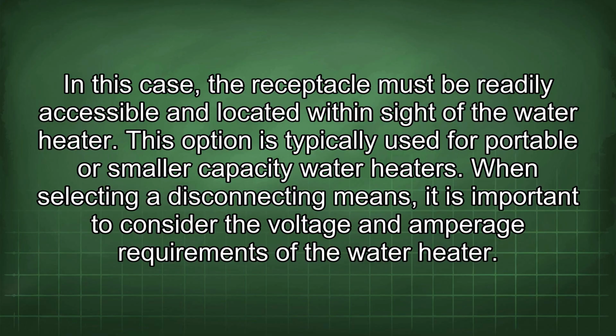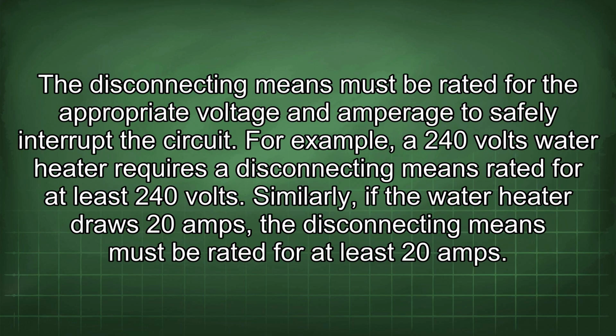When selecting a disconnecting means, it is important to consider the voltage and amperage requirements of the water heater. The disconnecting means must be rated for the appropriate voltage and amperage to safely interrupt the circuit. For example, a 240 volts water heater requires a disconnecting means rated for at least 240 volts. Similarly, if the water heater draws 20 amps, the disconnecting means must be rated for at least 20 amps.